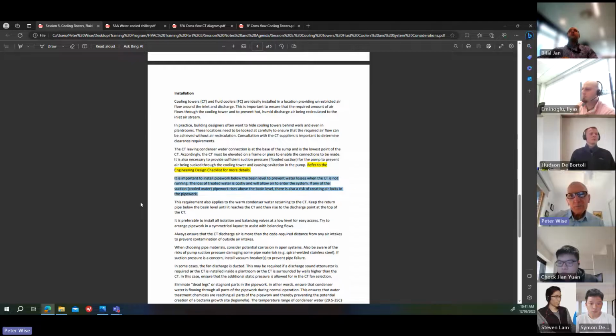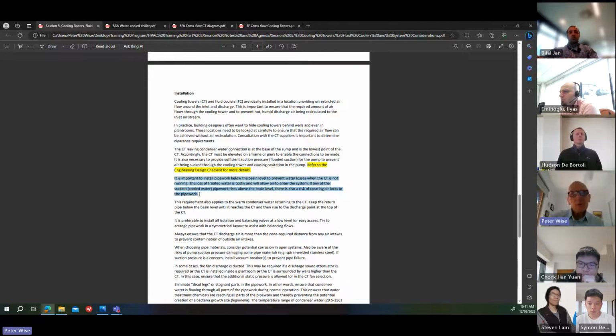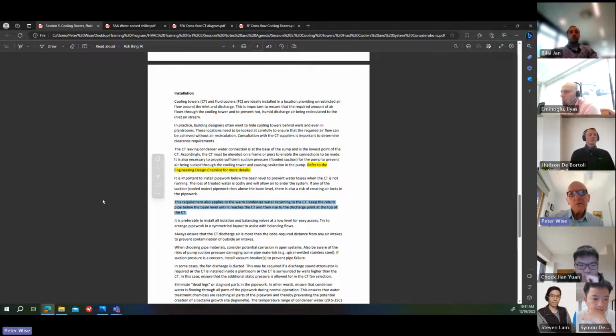You will have check valves on the pumps, but when there's very low pressure, when the pumps aren't operating, water can leak past the check valves and find its way out. So it's important to keep all the pipework below the level of the basin as much as you can. And this also applies to the returning water, the warm condenser water returning to the cooling tower. Keep the return pipe below the basin level until it reaches the cooling tower, and then raise the pipe up to the discharge point at the top of the tower.